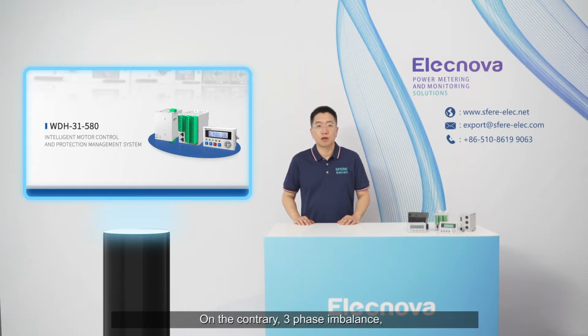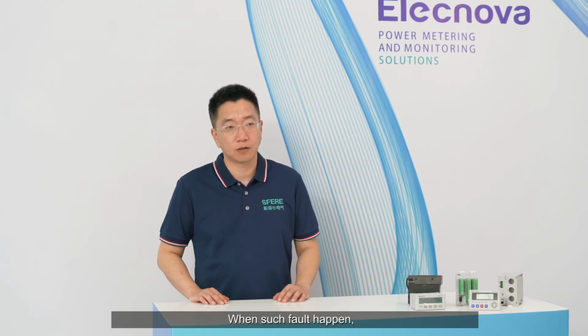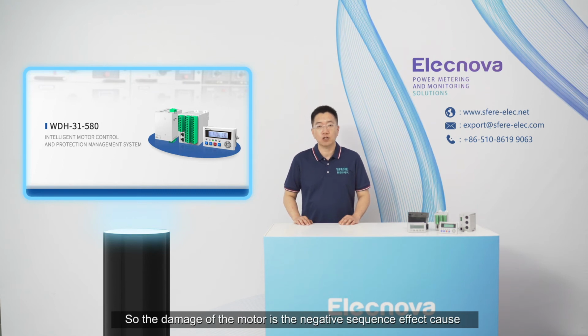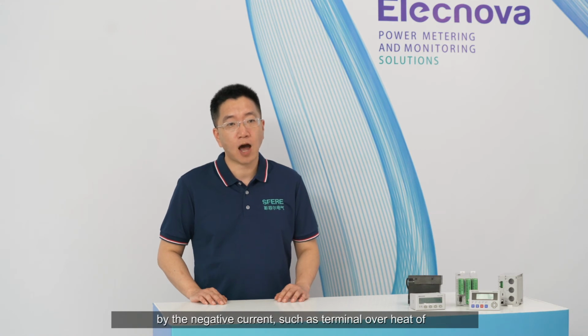On the contrary, three-phase imbalance, single-phase ground connection, or phase-to-phase short circuit are the major phenomena of the asymmetrical faults. When such a fault happens, there is no obvious overcurrent, but the negative current increases significantly. So the damage to the motor is the negative sequence effect caused by the negative current, such as terminal overheat of the motor, rotor vibration, and the decrease of the start torque.